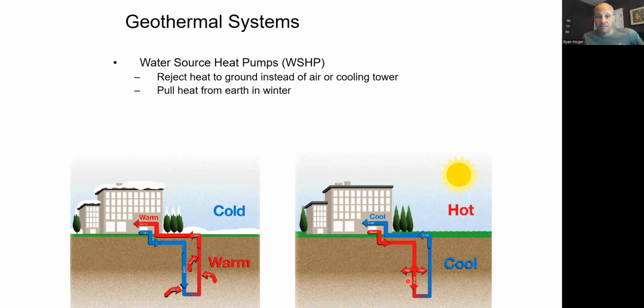Then come wintertime, when the heat pumps start flipping over into the heating mode, those heat pumps can pull heat out of the ground, and not just from a ground temperature that started out at 60 degrees or whatever it was, but now it's starting at 80 degrees because I banked heat there all summer long. So in the summertime, you're banking heat in the ground. The ground is basically a ginormous storage tank for heat. I bank it there all summer, and in the wintertime, I take it back out, right? It's a pretty cool idea.